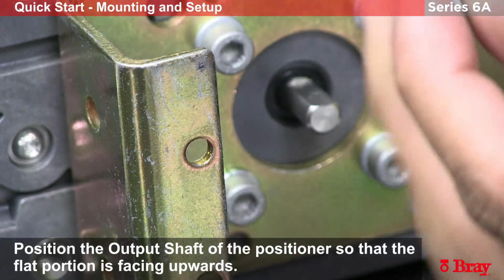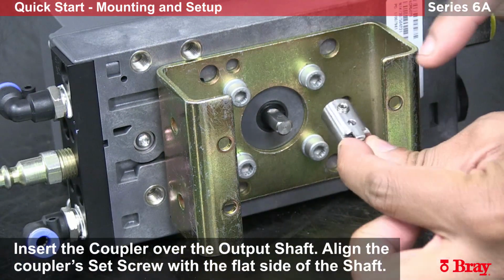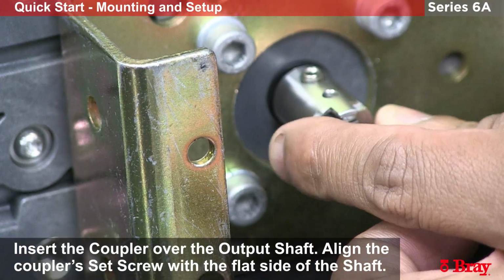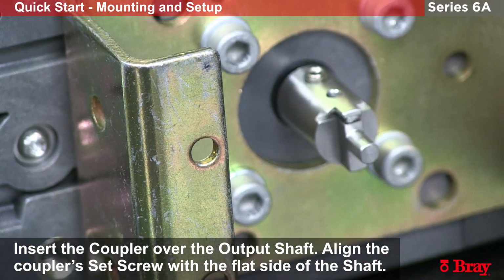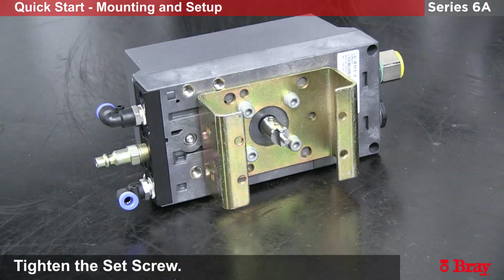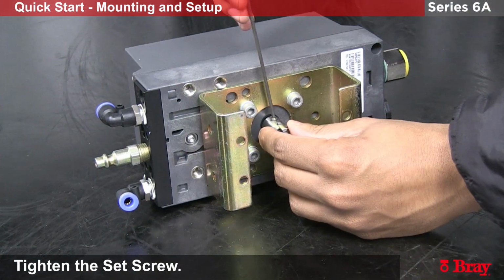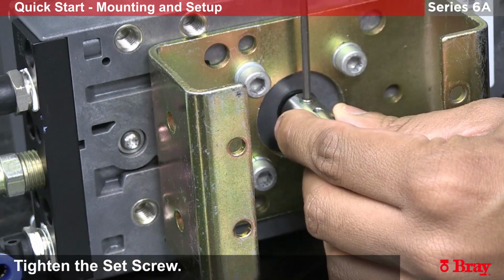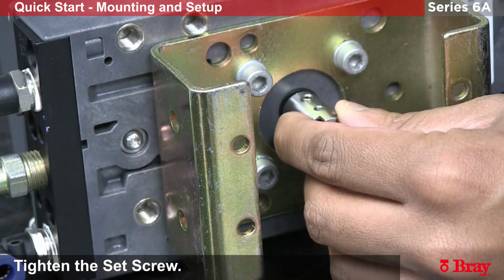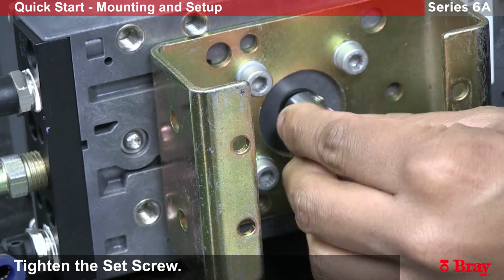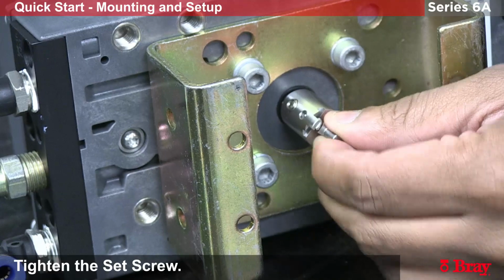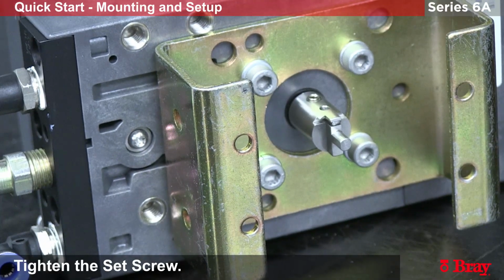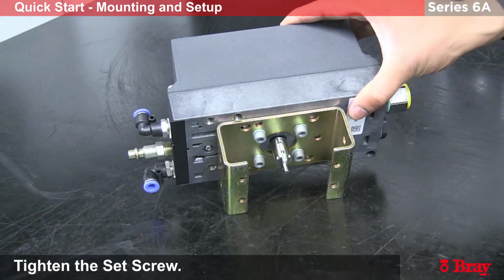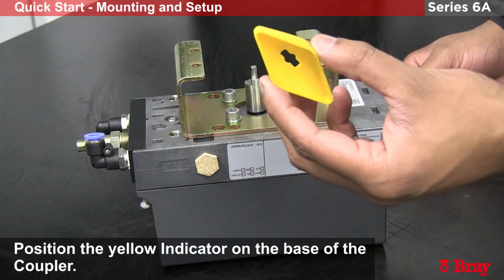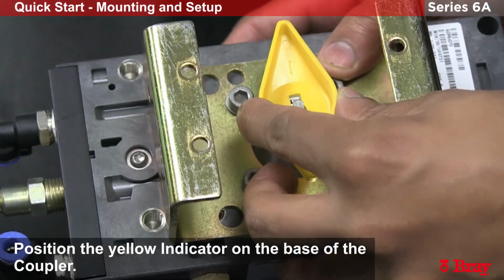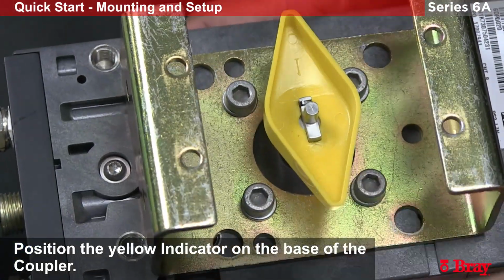We will then take the coupler with the nut facing up and place it onto the shaft. Using a hex wrench, we will tighten the lock bolt. Ensure that you are rotating the shaft of the positioner while turning the coupler, and you're getting no slippage. Next, we'll add the yellow indicator arrow. This is an interference fit onto the coupler, so place it snugly.